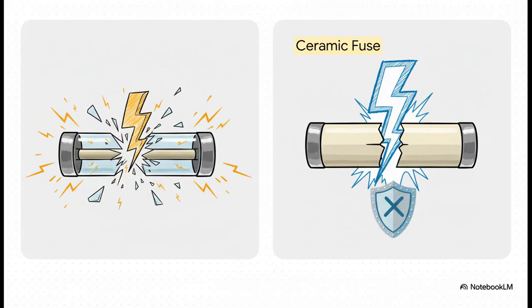And it gets even deeper. The actual material the fuse is made of is a huge safety feature too. That little glass fuse you see everywhere might only be rated to safely interrupt, say, a 35-amp fault. If the short circuit is bigger than that, the fuse itself can literally explode or create an electrical arc, which is a whole new problem. But a ceramic fuse is much tougher. It can handle way higher fault currents, keeping everything contained and safe when things get really nasty.